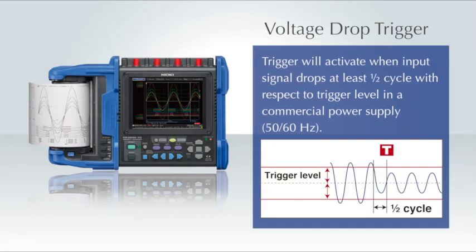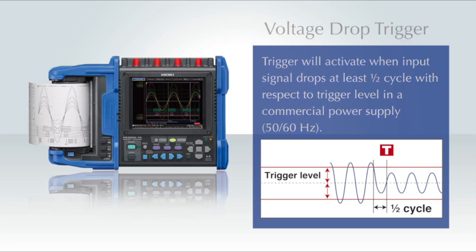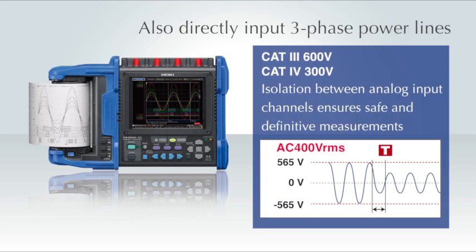The Hioki MR8880 Memory HiCorder can be set up with a trigger to detect a voltage drop on a commercial power line. In addition, the recorder is designed to be used safely in a CAT3 600 volt environment and offers completely isolated input.